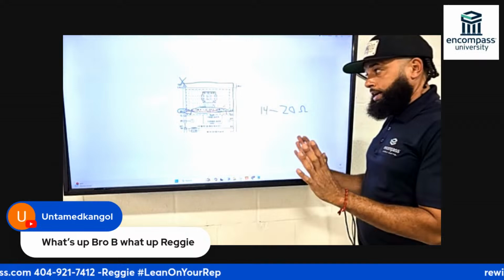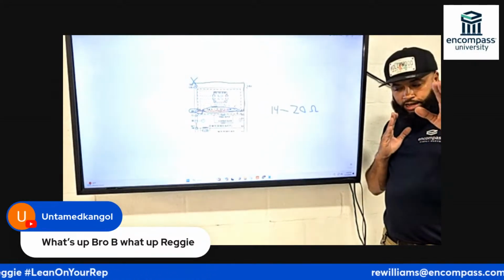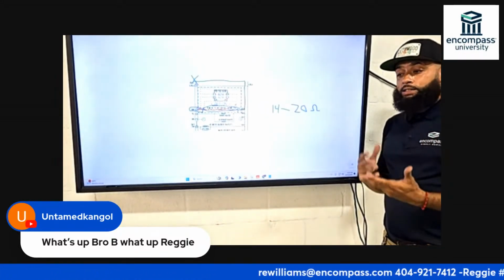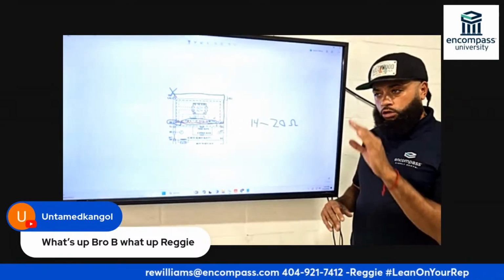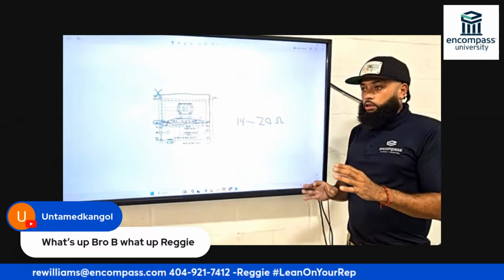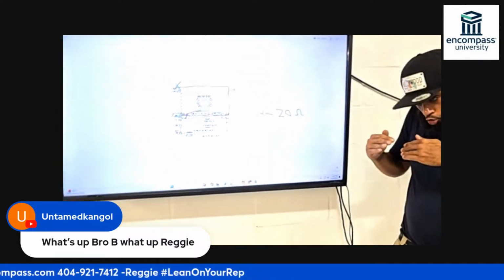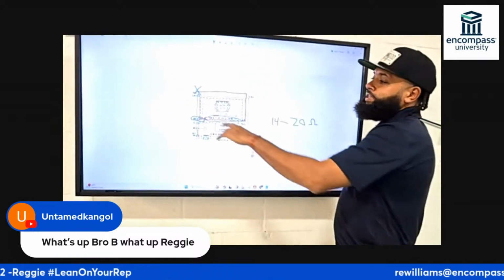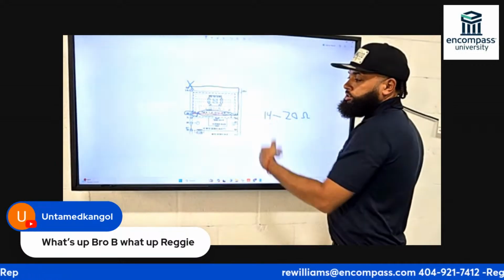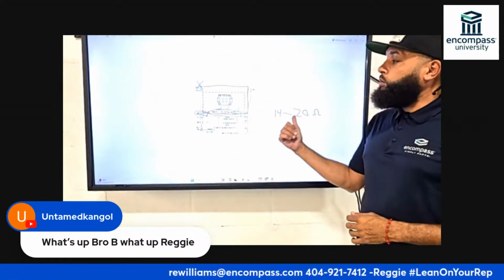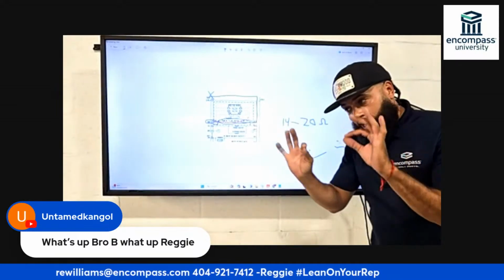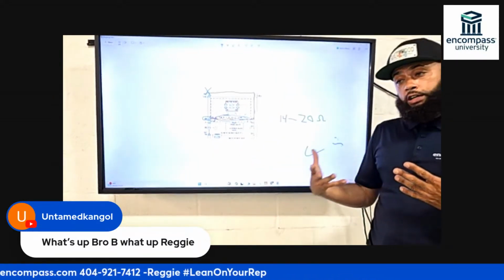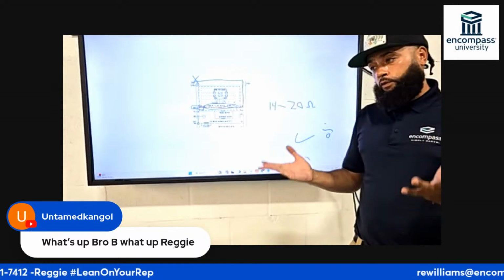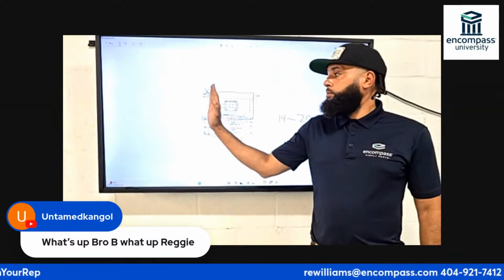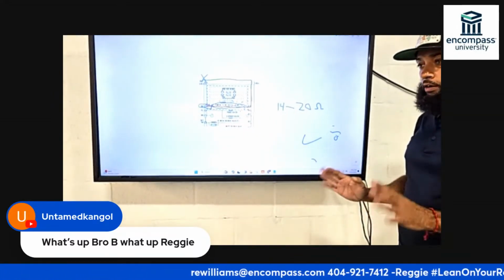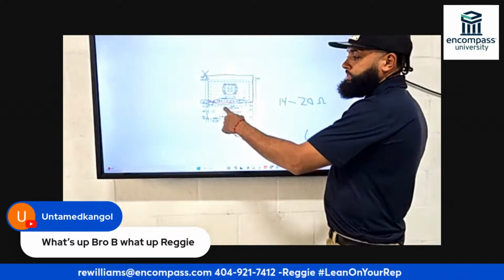My approach is to go to that fridge, which has a test mode. In that test mode you can turn on defrost mode, and once you do, this board will send output voltage to the heater. That's when I want to check that the board is sending 120 volts. At that point I can rule my board out as a culprit for now.